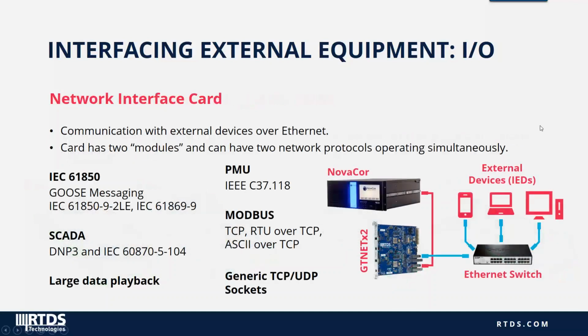The interface with external equipment can also be created based on standard compliant communication. To do so, we use this network interface card. So this card takes power system simulation data, assembles it into standard compliant packets, and then sends those out via Ethernet. And it can also, similarly, unpack the inputs coming from devices under test. And it can directly stream the protocols listed here in real time.